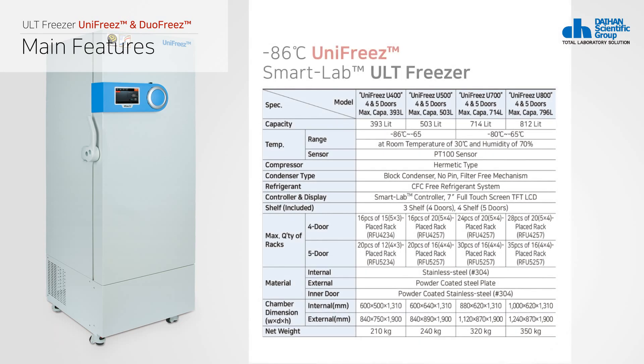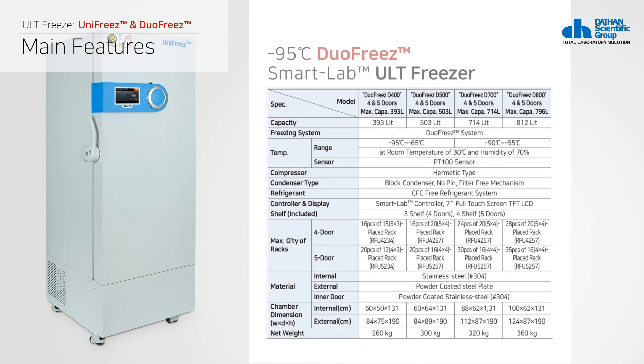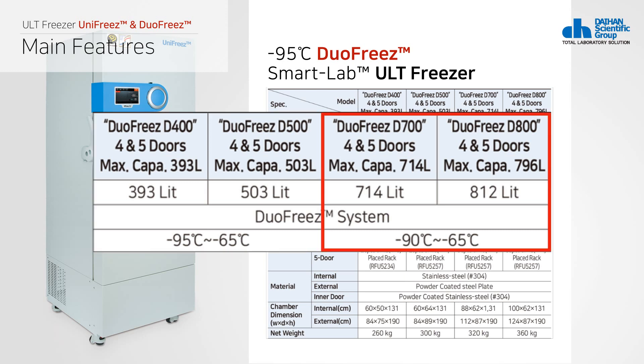Unifreeze consists of 400, 500, 700, and 800 series. Unifreeze U400 and U500 can be used from minus 86 to minus 65 degrees Celsius. Unifreeze U700 and U800 can be used from minus 80 to minus 65 degrees Celsius.